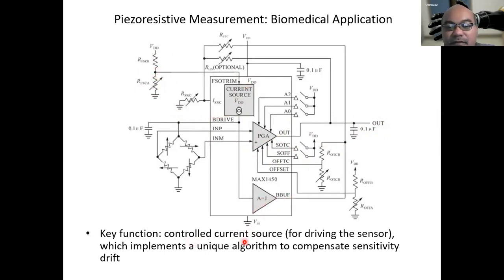So this is a controlled current source for driving the sensor. The excitation for the Wheatstone bridge comes from this current source node, which implements a unique algorithm to compensate for sensitivity drift.